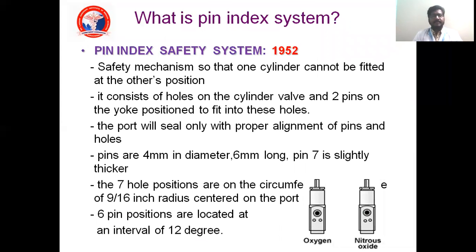What is pin index system? It is a very important aspect in cylinders. It is one of the safety systems in cylinders in high pressure system. Pin index safety system was invented in the year 1952, and it is one of the safety systems of the high pressure system, so that one cylinder cannot be fitted at another position. It consists of holes on the cylinder valve and two pins on the yoke position to fit into the holes. The port will seal only with proper alignment of the pins and holes.